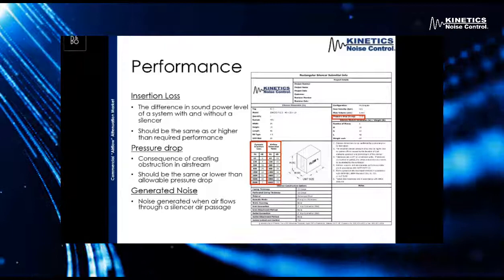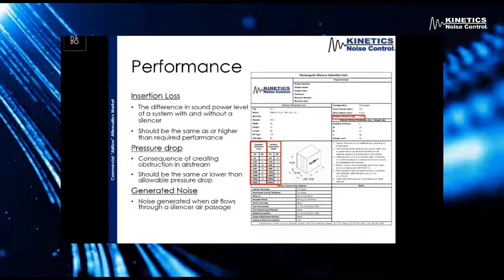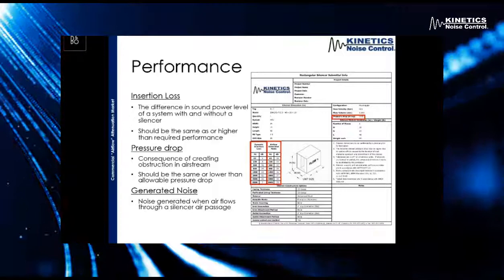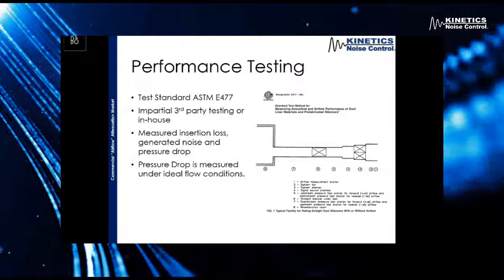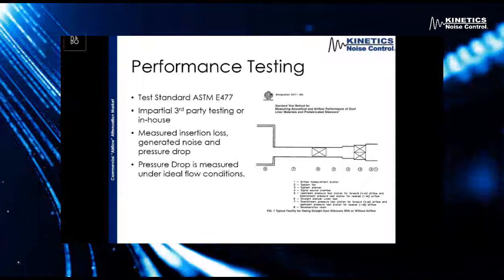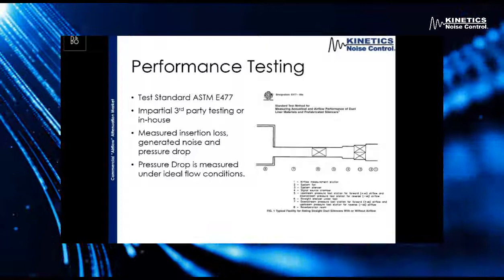There are some times we do need to consider generated noise — that's when we have rooms or spaces that require an NC-20 rating or lower. We're looking at spaces like performance halls, recording studios, things of that nature where sound is very, very sensitive. The way we get these performance numbers is through the ASTM E477 test standard. At Kinetics, we use impartial third-party testing — we send our silencers to get tested, and they use ASTM E477 to measure the insertion loss, generated noise, and pressure drop. What's important to note is that the pressure drop is measured under ideal flow conditions, and we'll get into why that's important in a couple of minutes.